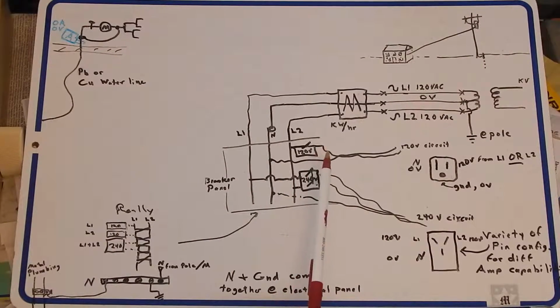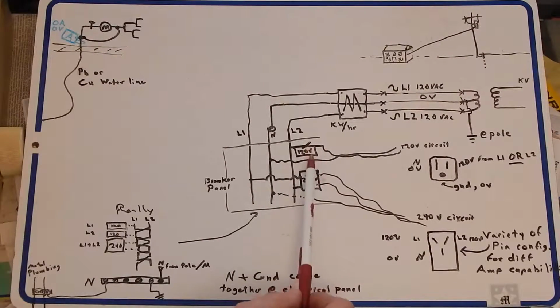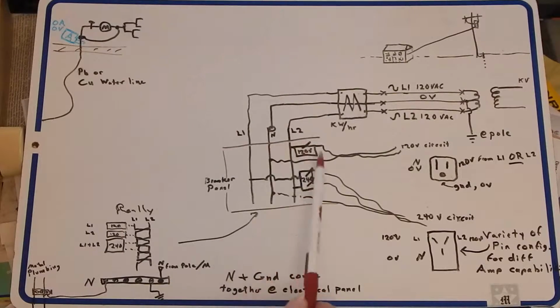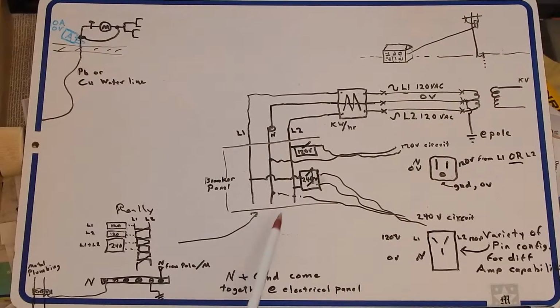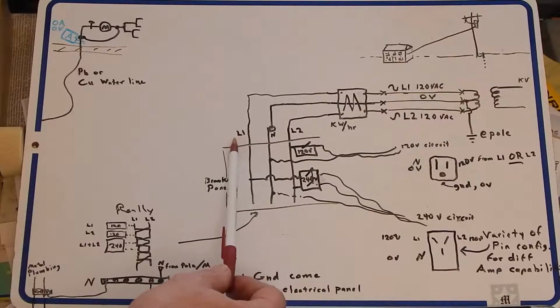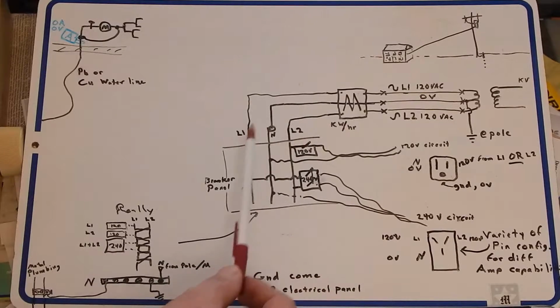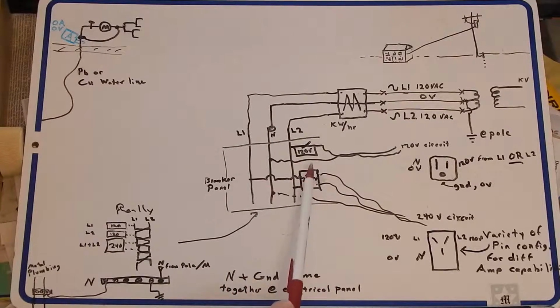So you've got mostly 120 volt breakers loaded in the box here, and half of them are going to be on L1 and half are going to be on L2. And then you've got a 240 volt breaker, which is connecting to both L1 and L2 and putting it out.